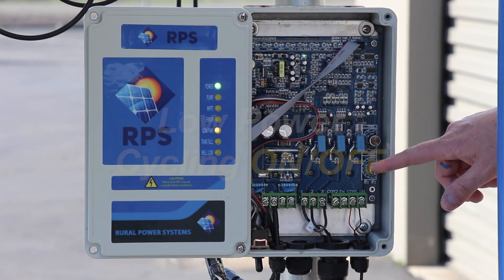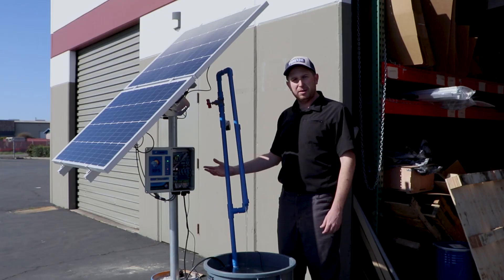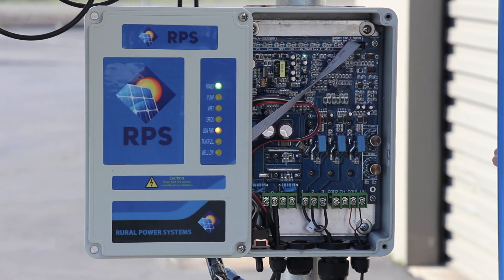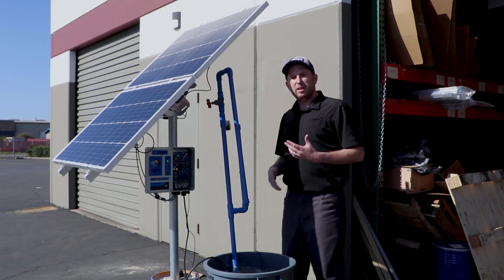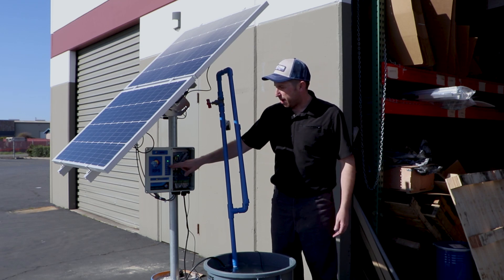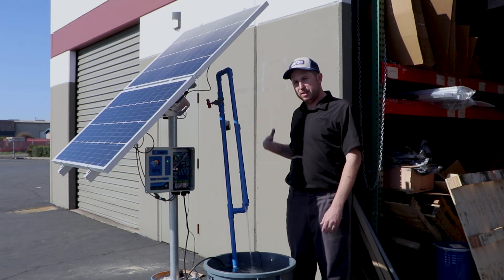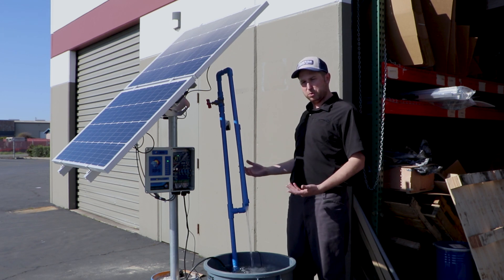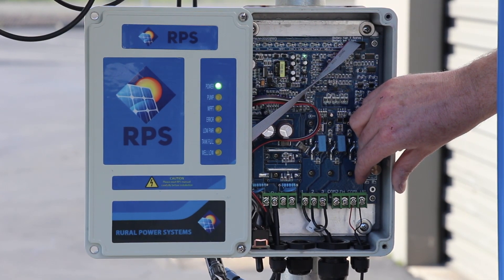Inside your controller there's a speed control that goes from zero to ten. Some users turn this down to match their well's production to their pumping volume in gallons per minute. Anytime you're troubleshooting, make sure this is turned up to ten. If it's turned down low, strange things can happen — such as the error light or low power light coming on even with plenty of sunlight. Turn it back up to ten, confirm everything is working, then turn the speed dial back down to match your well if desired.